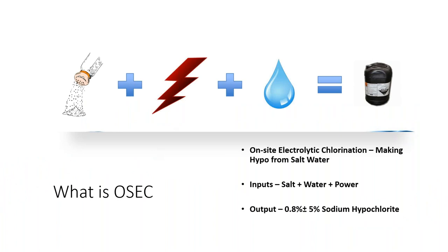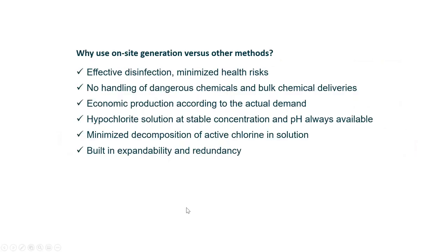What is OSEC? Basically, OSEC generates 0.8% sodium hypochlorite on site by just using salt, water and power. So why do we prefer on-site generation versus other methods? What is the benefit of using an on-site sodium hypochlorite generation system compared to buying commercial sodium hypochlorite in bulk and calcium hypochlorite? Firstly, it's an effective disinfection and it minimizes health risk.